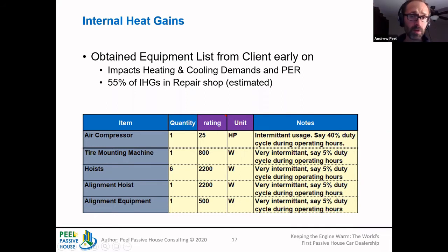What we had to do is work with the client on how they use the equipment and estimate their loads and ultimately how many internal heat gains they would emit. So we worked through it piece of equipment by piece of equipment. And you can see we estimated about 55% of the internal heat gains was due to this equipment. But that's estimated, right? We couldn't point to any previous project with monitoring data or expected energy use of these machines. So in the end, it was an estimate.